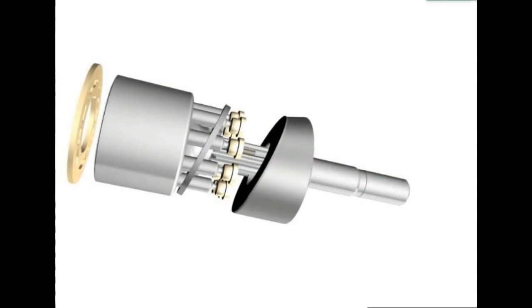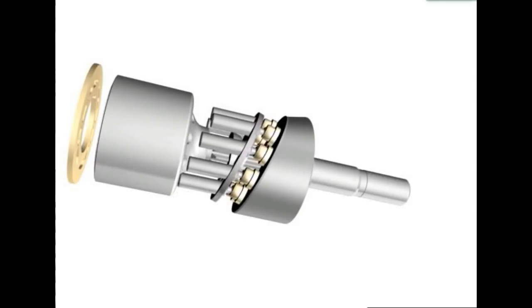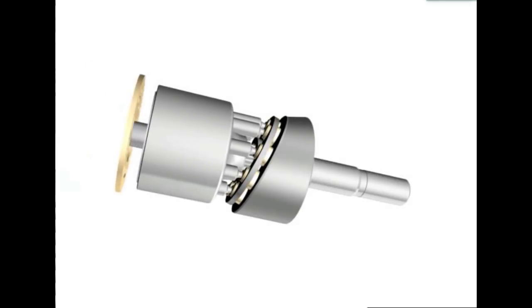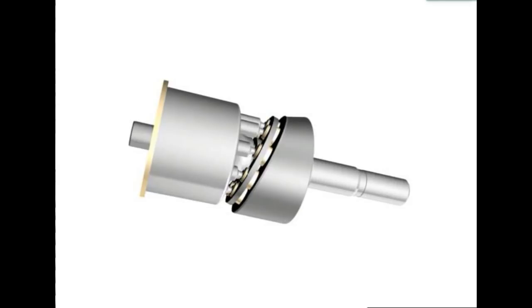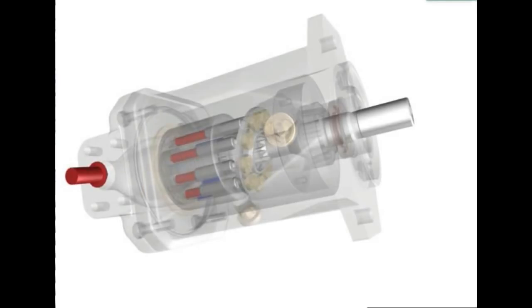The cylinder barrel is fixed to the output shaft. The pistons reciprocate in and out of the cylinder barrel on an axis parallel to the output shaft. A bias spring and the shoe plate hold the piston shoes against the swash plate and the barrel against the valve plate. The swash plate sits at an angle to the pistons.